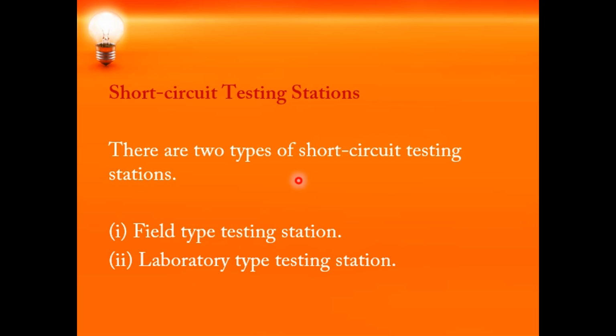So in the field type testing station, the power required for testing of the circuit breaker will be derived from a large system. The circuit breaker will be connected to the power system, and a large amount of power is easily available. So this method of testing is economical for testing of very high voltage circuit breakers. But even though it gets a large power for testing and it can be easily conducted without any setup, it has some drawbacks. So what are the drawbacks?